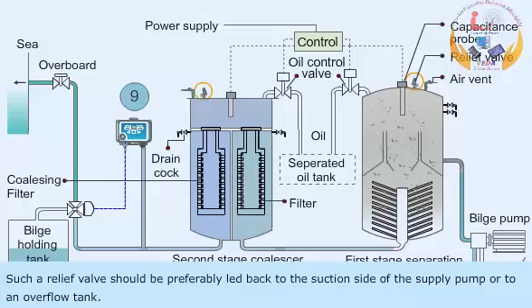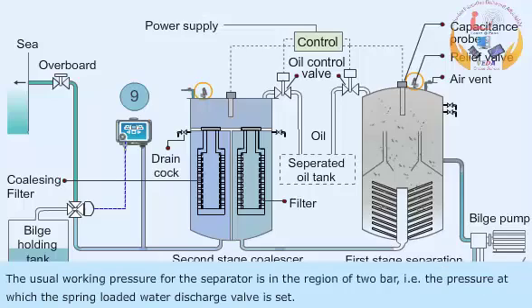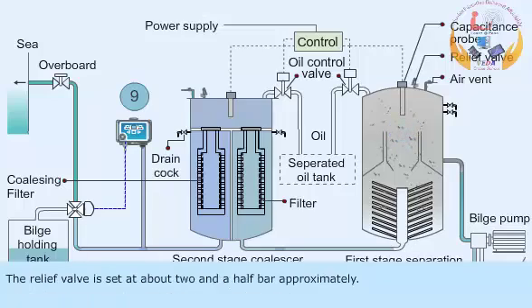Such a relief valve should preferably be led back to the suction side of the supply pump or to an overflow tank. The usual working pressure for the separator is in the region of 2 bar, which is the pressure at which the spring-loaded water discharge valve is set. The relief valve is set at approximately 2.5 bar.